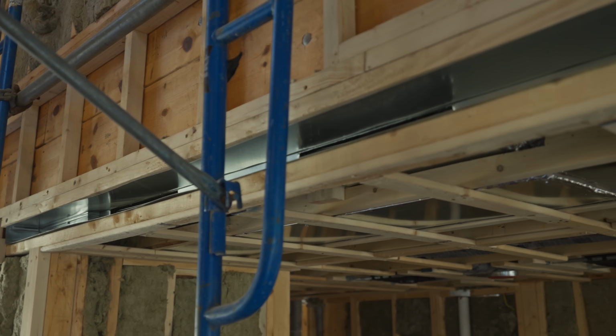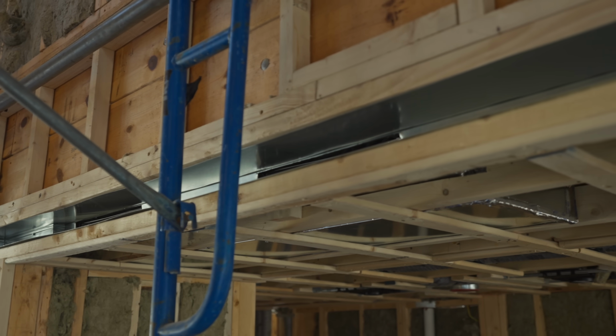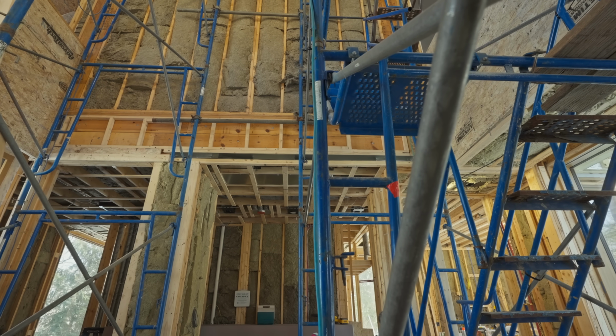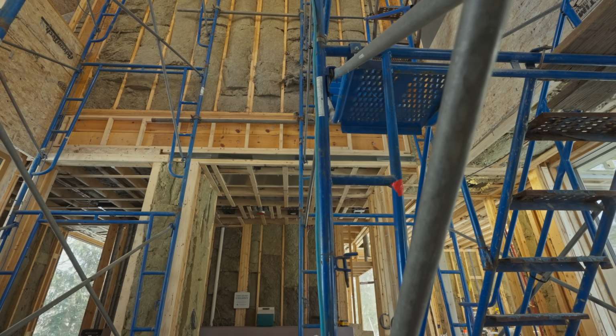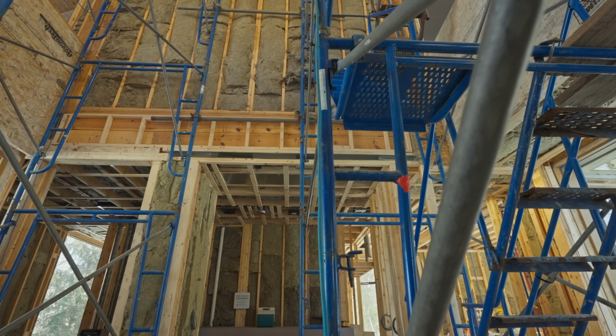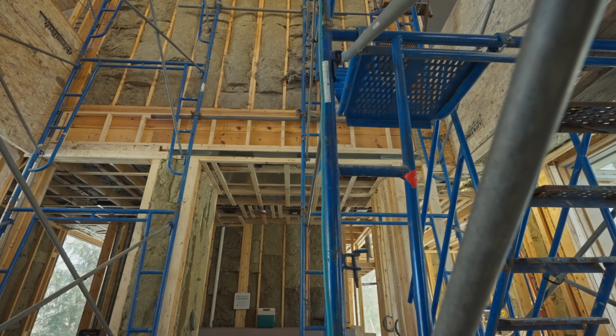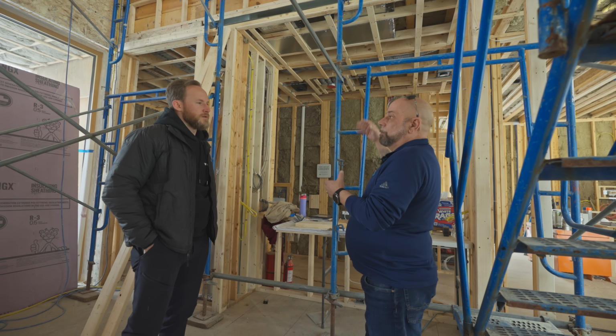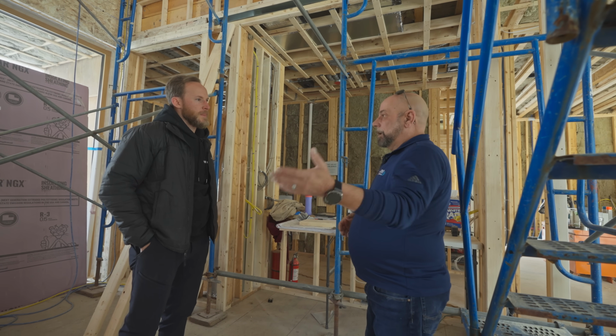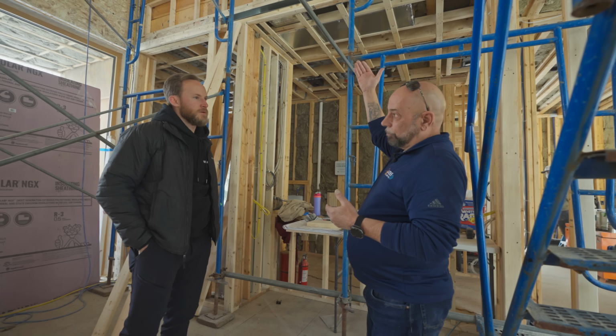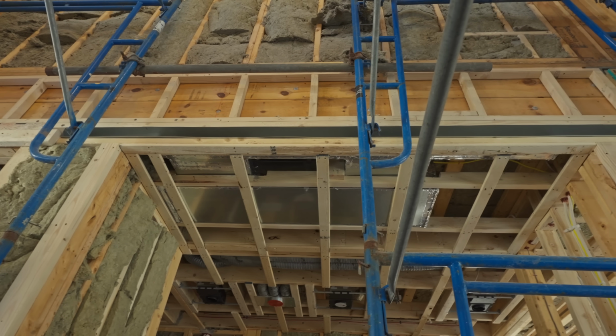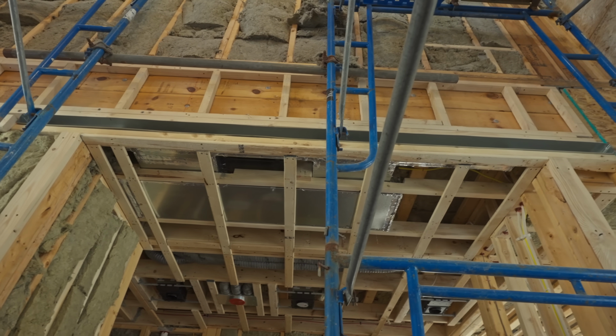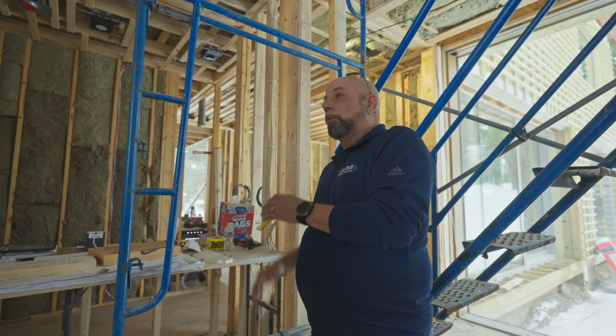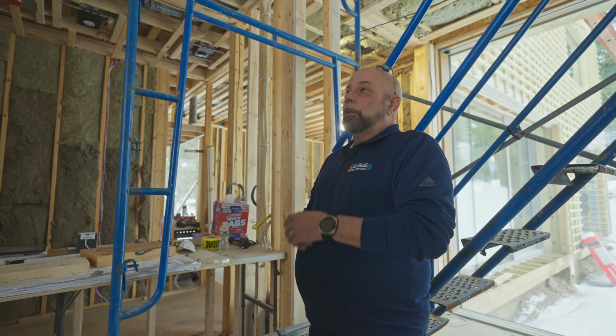What's the benefit of having it up high? Heat rises, cool air settles, so we're not at the highest point, we're kind of in the middle point, helping both the heating and cooling. In some instances you can't do that, with a return on the floor versus a return elsewhere, but here it worked out really well where we're not way up high and not really down low, we're in the middle, and that's where we want to pull the air from.